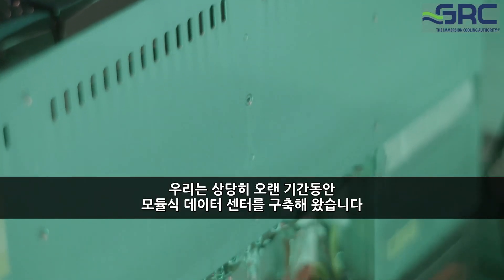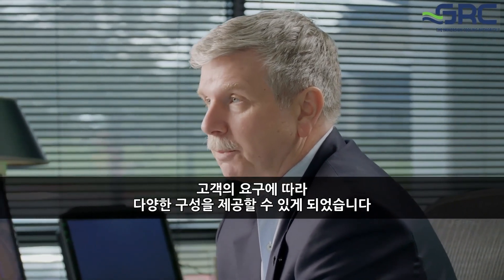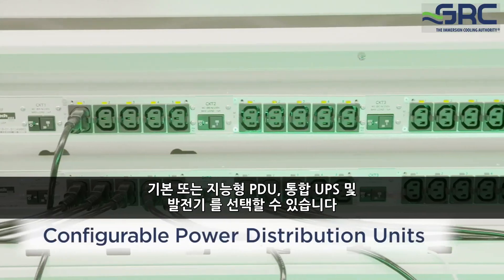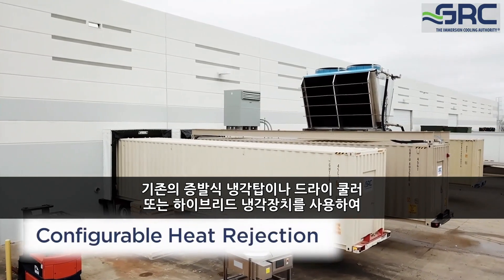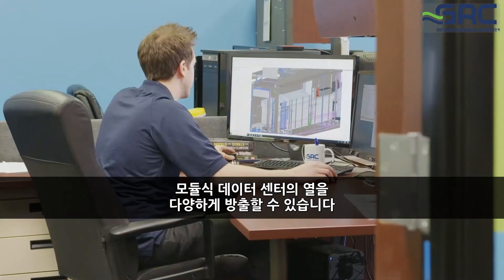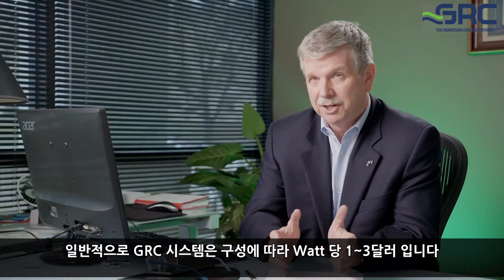We've been building these modular data centers for quite some time, and what that's done for our customers is it's enabled us to provide a broad range of configurations depending on what the customer's needs are. You can choose whatever rack density you want — 25 to 100 kilowatts, dumb or intelligent PDUs, integrated UPSs or discrete UPS and gensets, multiple ways for you to reject the heat out of the modular data center, whether that's with traditional evaporative cooling towers, a dry cooler, or a hybrid cooler. When you mix and match all of those things, it gives you a lot of flexibility to meet your requirements, and you can do it in a very cost-effective way. Typically our systems are $1 to $3 a watt, depending on how complex your configuration is.